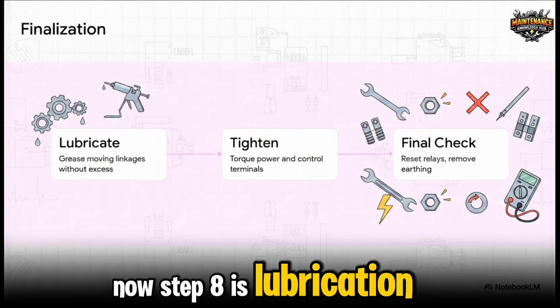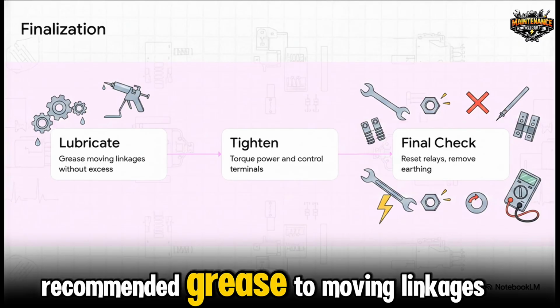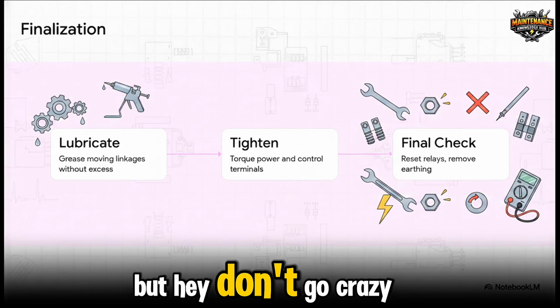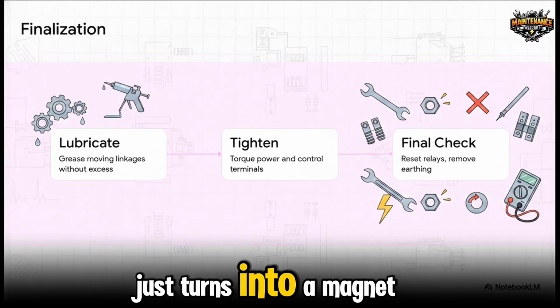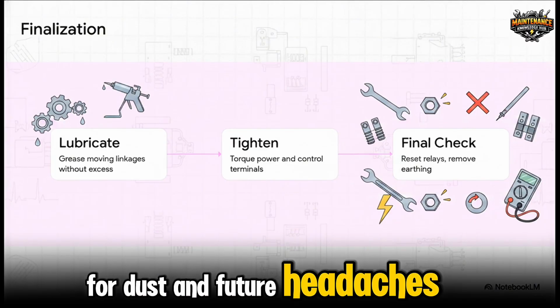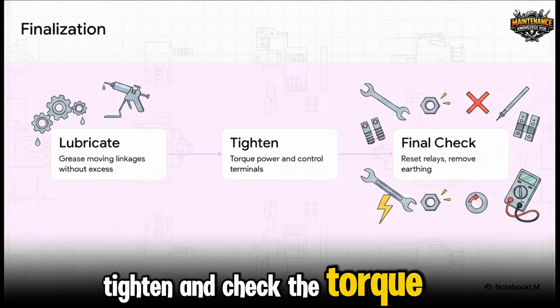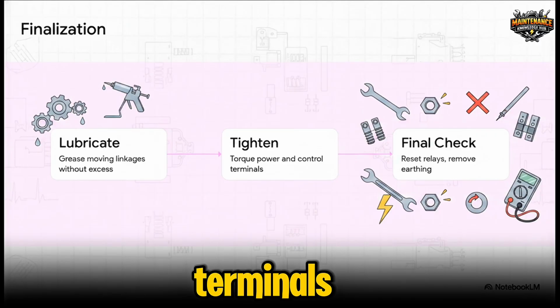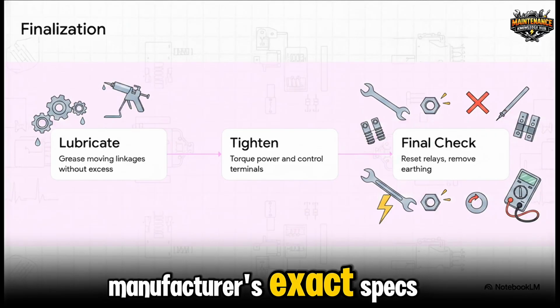Step 8 is lubrication. Apply the specific recommended grease to moving linkages, but hey, don't go crazy here. Over-lubricating just turns into a magnet for dust and future headaches. Step 9, tighten and check the torque on all power and control terminals. You have to hit the manufacturer's exact specs.